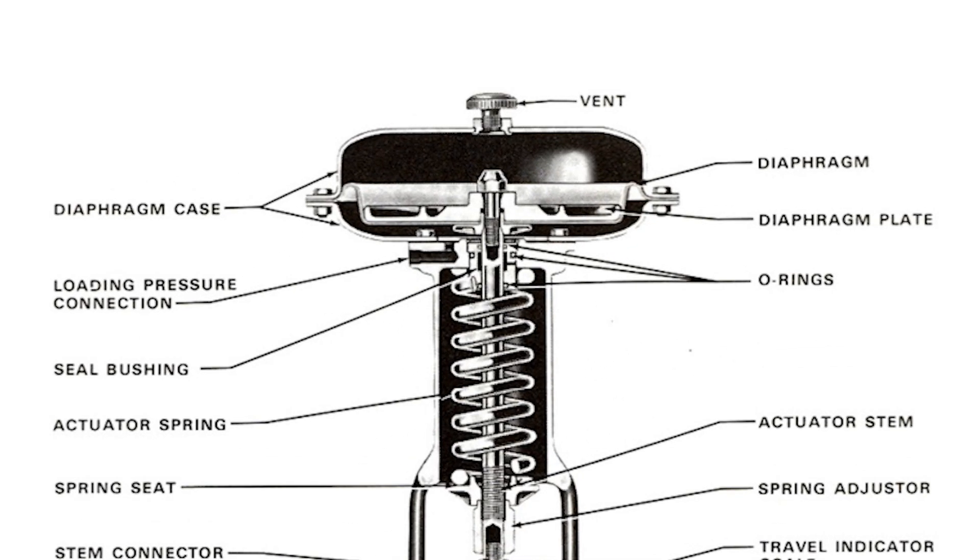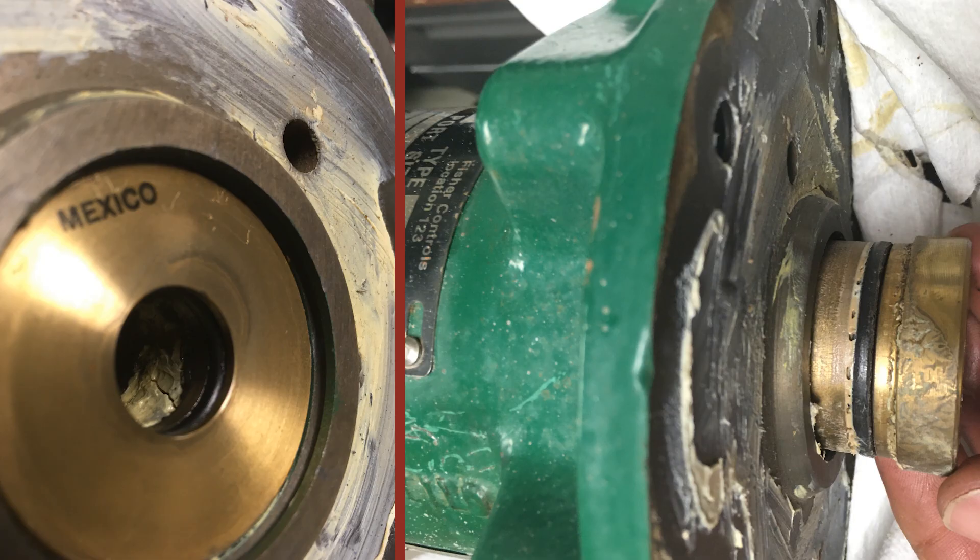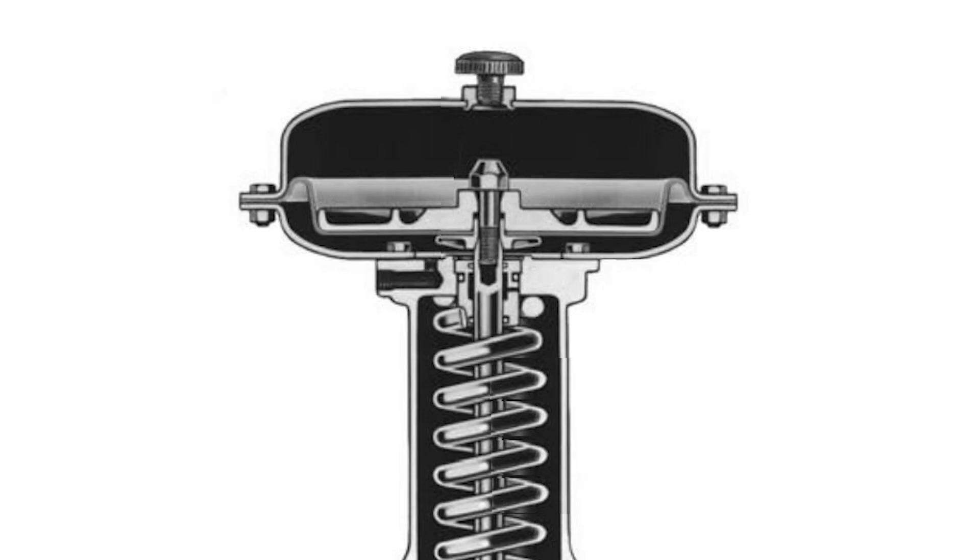On reverse acting actuators, there are three O-rings that are used to isolate the actuator diaphragm chamber from the spring chamber. If one of these O-rings fail, air will be allowed to leak into the spring chamber.